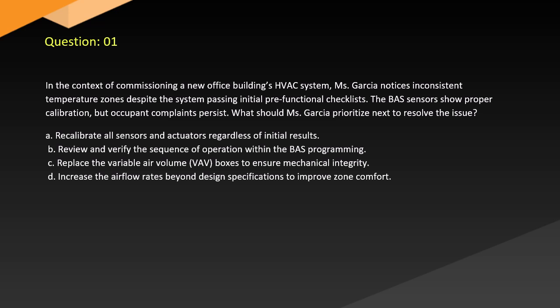Question 1. In the context of commissioning a new office building's HVAC system, Garcia notices inconsistent temperature zones despite the system passing initial pre-functional checklists. The BAS sensors show proper calibration, but occupant complaints persist. What should Garcia prioritize next to resolve the issue?